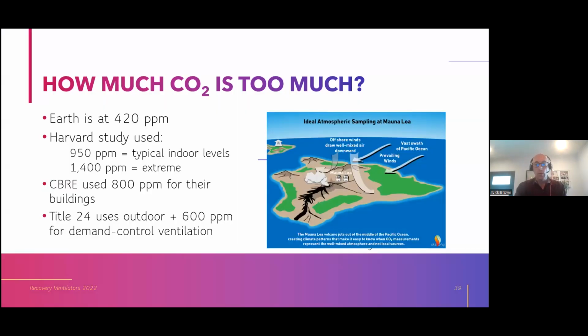Okay, one more note on CO2, because I found the science is unsettled here. Mauna Loa is where we measure the Earth's overall CO2 concentration. It's at about 420 parts per million. So that's what you're starting with. The Harvard study used 950 as typical indoor levels and 1400 as extreme. I sat in on a webinar by the sustainability woman from CBRE, and she said they're trying to achieve 800 parts per million in their high performance buildings. And Title 24, the non-res standards use outdoor concentration plus 600 parts per million as the trigger for demand control ventilation. So there's some data points for you to consider on how much is too much.